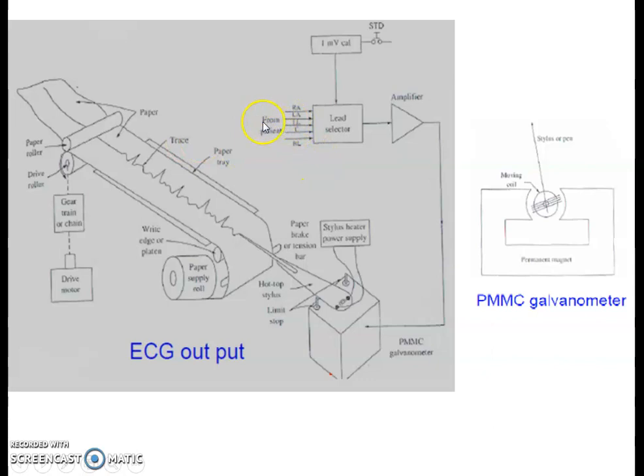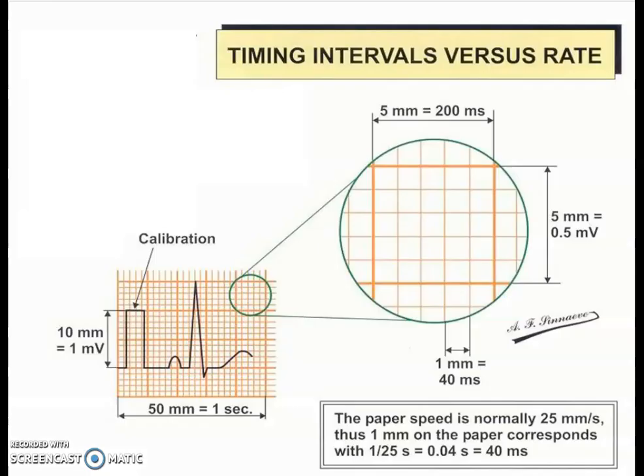As per the signal which comes from the patient's body, this heated stylus moves over the heat-sensitive paper in order to give good frequency response and in order to record the ECG signal which is in the range of hundreds of hertz. The ECG paper generally contains a signal where the first signal itself is called the calibrating pulse. This pulse is of 1 millivolt height, which is followed by your original ECG signal.